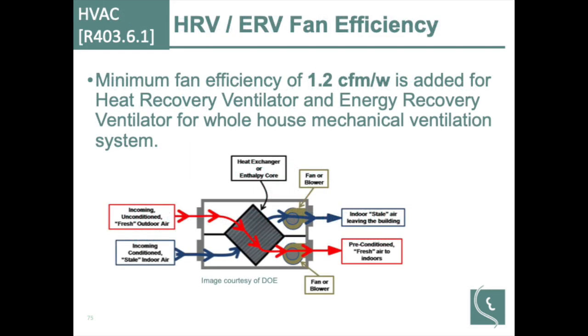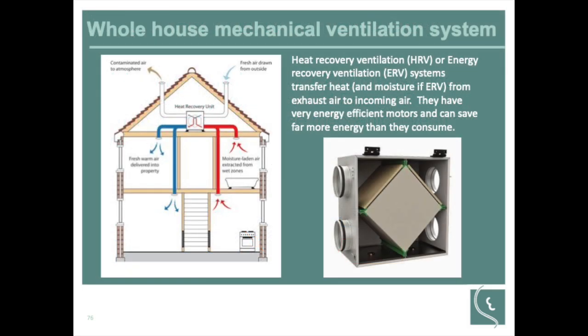Fan efficiency, I don't know how frequently we run into too many issues with this, with HRVs and ERVs. How many of you are seeing these installed as part of normal practice in residential yet? Not really. Okay. These tend to be a more premium product. But we do call out there is a fan efficiency requirement. And again, it's because this is running 24/7, so any efficiency gain here is really going to be beneficial.